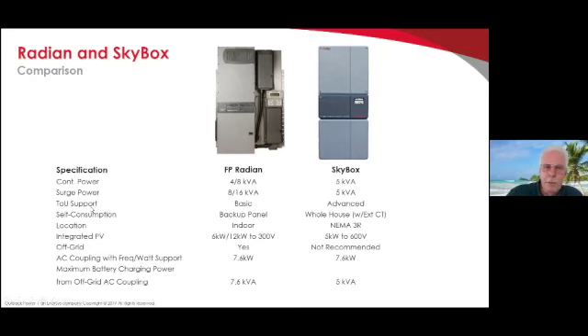We also have some time of use smart grid features, if you will, and it's a little bit basic with Radian. We can drop the grid up to 3 different times a day. So if you're trying to match the rate structure with your utility, you can do that. Skybox is more advanced. You can put in the entire rate schedule. You can put an external CT at the main panel and self-consume all the way out to the main panel. So it's got some nice capabilities to it.